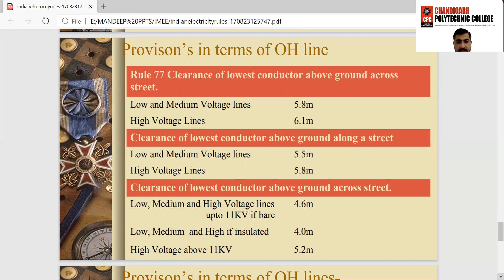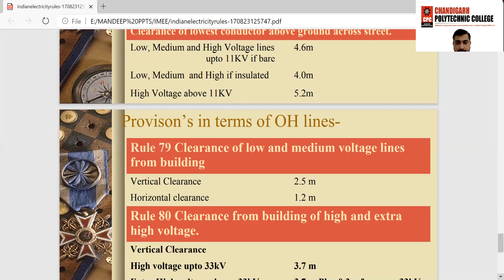Under Rule 79, clearance of low and medium voltage lines from any kind of building. The minimum vertical clearance required is 2.5 meter above the building, and the minimum horizontal clearance on sideline required is 1.2 meter. Under Rule 80, the clearance from building of high and extra high voltage.